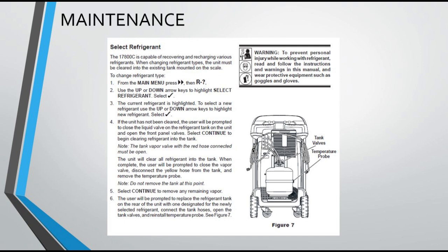Select Continue to begin clearing refrigerant into the tank. Note, the tank vapor valve with the red hose connected must be open. The unit will clear all refrigerant into the tank. When complete, the user will be prompted to close the vapor valve, disconnect the yellow hose from the tank, and remove the temperature probe. Note, do not remove the tank at this point. Select Continue to remove any remaining vapor.